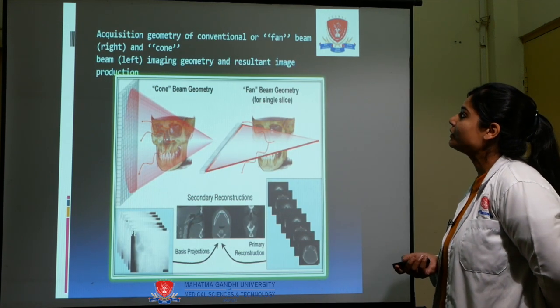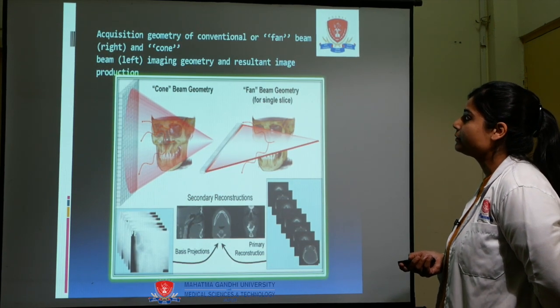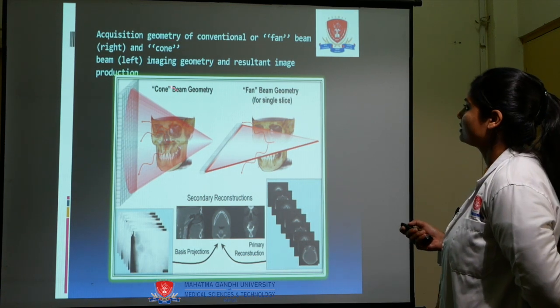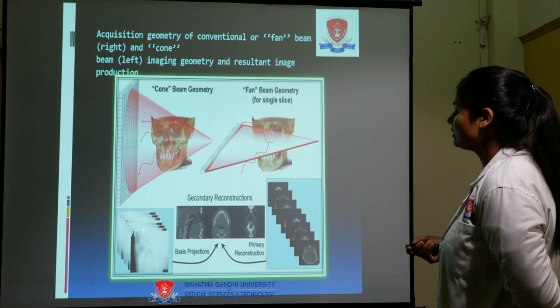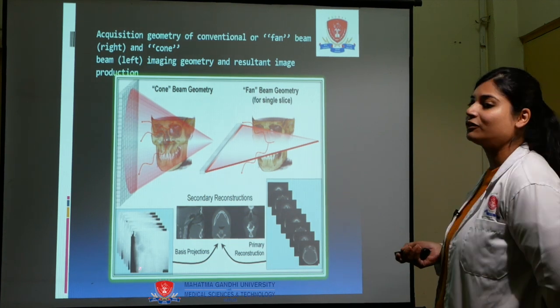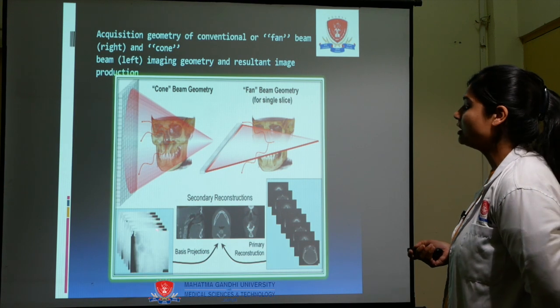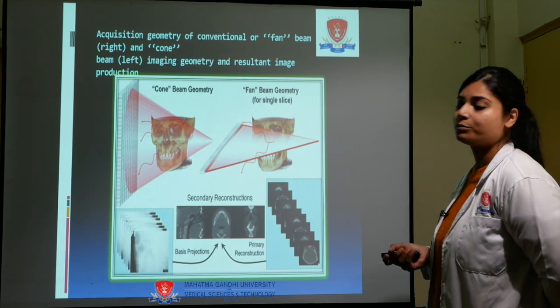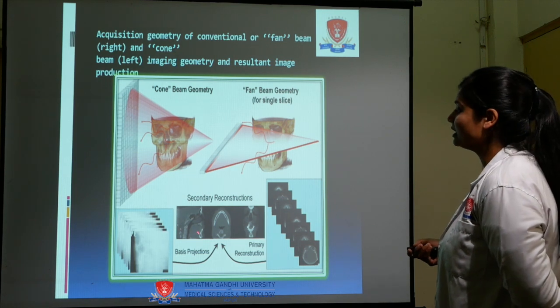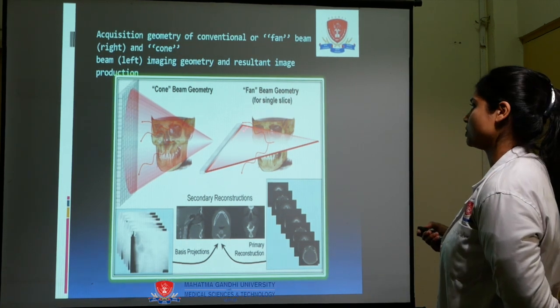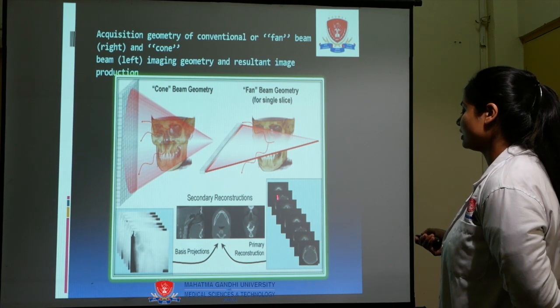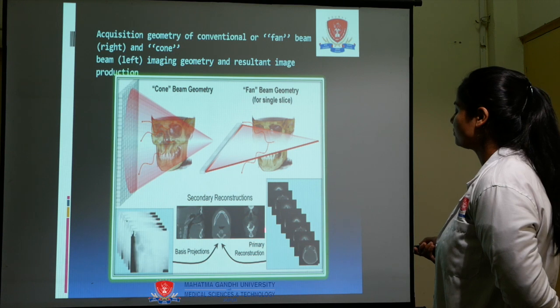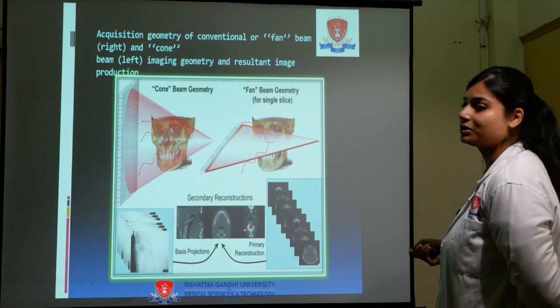This shows the acquisition geometry of a conventional fan-shaped beam on the right side and a cone-shaped beam on the left side. The cone beam geometry captures multiple slices, cumulatively known as basis projections. Secondary reconstruction is done by the computer, giving the 3D image in all three directions. The fan-shaped beam captures images only in axial sections, and primary reconstruction gives the 3D image.